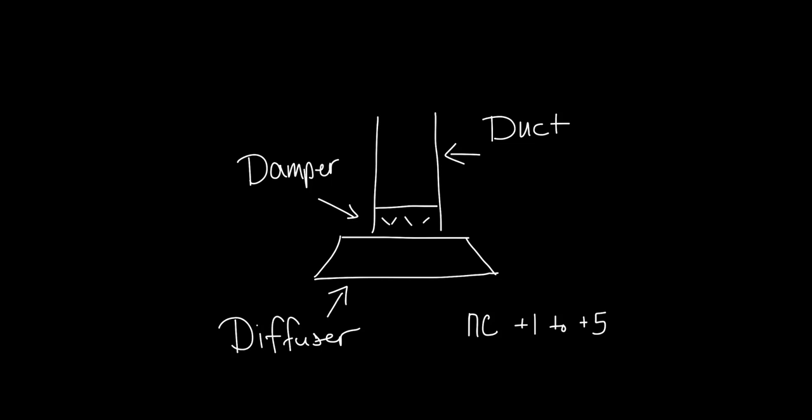What RP-1335 found from that set of tests is that the damper would drive the sound up by 1 to 4 NC depending on the airflow and unit size. This makes sense as you are adding material into the airstream which is going to produce sound as well as disrupt the airflow slightly.